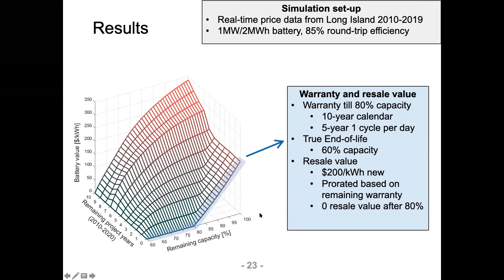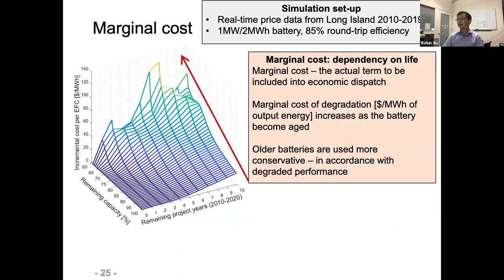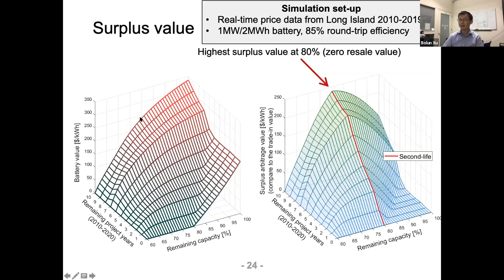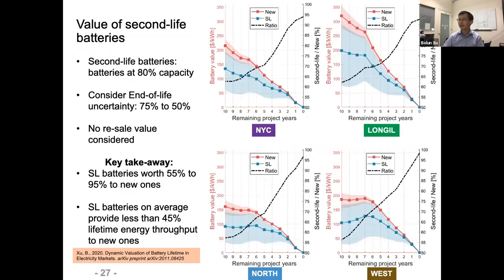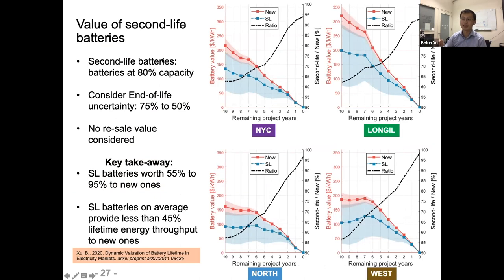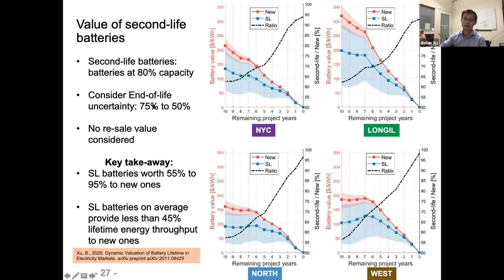Question about why second-life batteries are less economical than new ones. For a new battery you can use it from 100% capacity down to anywhere between 75–50% capacity. For a second-life battery you start at 80% — so you have much smaller capacity and much less available lifetime. The intuition for second-life batteries is that they are retired from electric vehicles: degraded too much for EV mileage or performance requirements, but still able to charge and discharge well enough for grid power system applications.